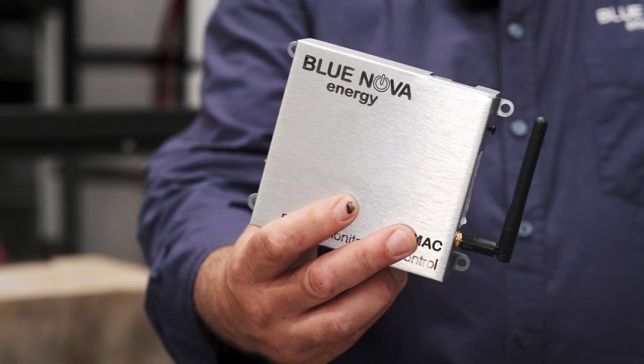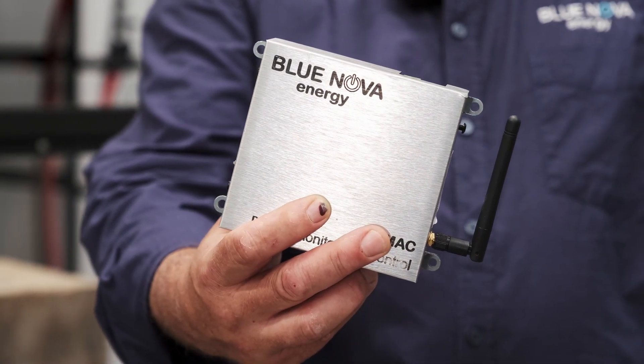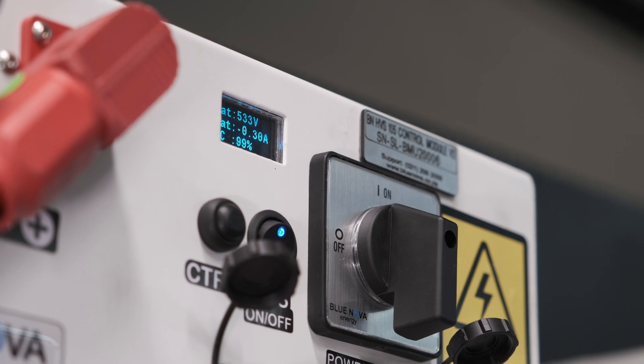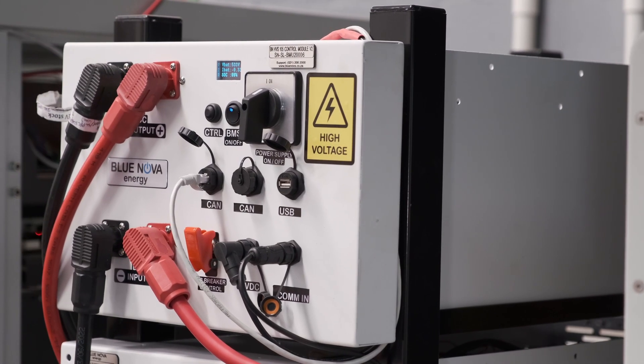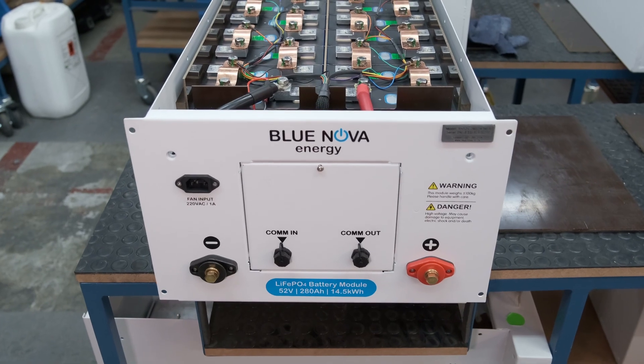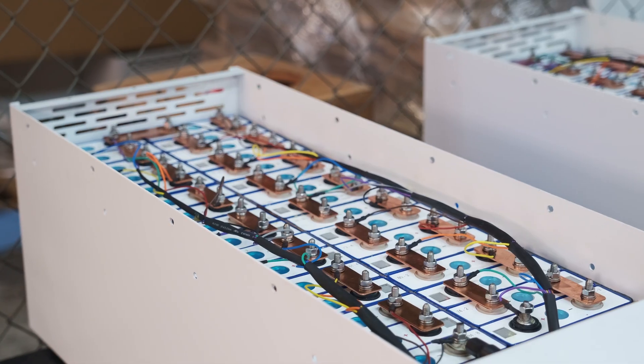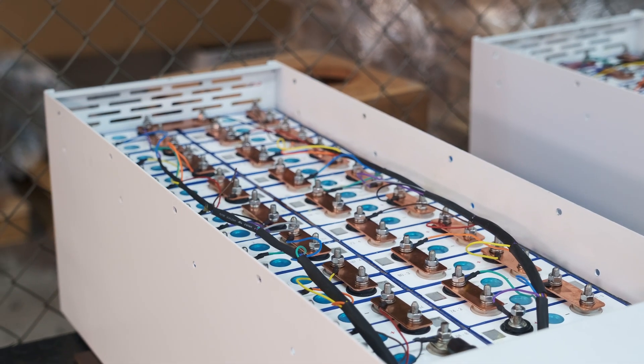The BMAC is 100% compatible with the new HV series inverter as well as our batteries. The compatibility test will allow the use of the BlueNova 105 amp hour high voltage series as well as the 280 amp hour high voltage series. You're going to have 33 to 55 kilowatt hours in steps of 11 kilowatt hours, and then 116 kilowatt hours in steps of 14.5 kilowatt hours, all the way up to 288 kilowatt hours.